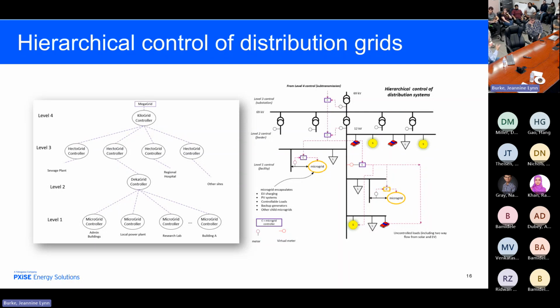We're thinking initially, let's take a baby step. Let's go to a pure hierarchy, no peer-to-peer communication, only parent-child communication. And the other concept is that these microgrids do not have to be associated with hardware. They can be virtual microgrids. Any point in the grid, here's one here. There's no switch and no meter here, but I can estimate what the real and reactive power flow are at that point and use an estimate of the grid.